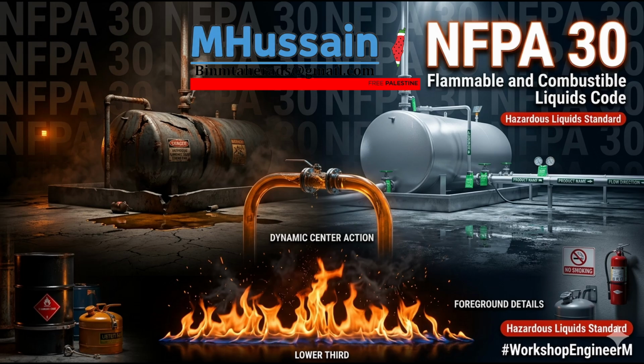Precisely. So NFPA 30 strictly dictates that emergency relief venting must be precisely sized to prevent the internal pressure from exceeding a gauge pressure of just 2.5 psi, or 20% of the tank's calculated bursting pressure, during a fully engulfing fire. 2.5 psi. Again, it sounds so delicate for a structure built from thousands of tons of welded steel. But a flat-bottomed AST is fundamentally not a pressure vessel. It is engineered to securely contain the static downward weight of the liquid column. It is highly vulnerable to outward pneumatic pressure.